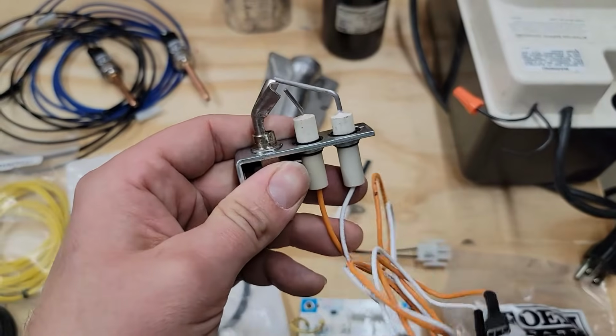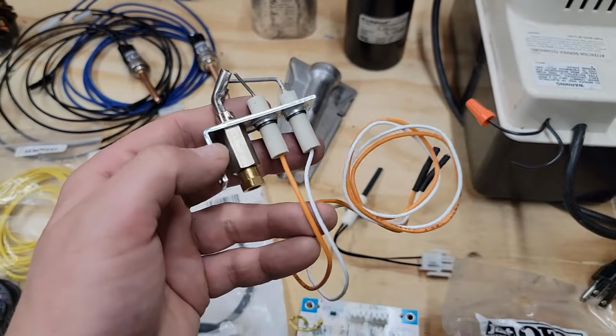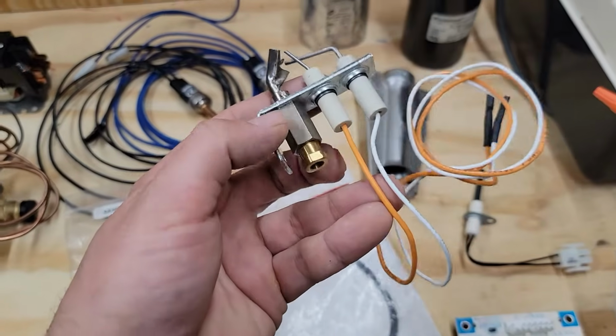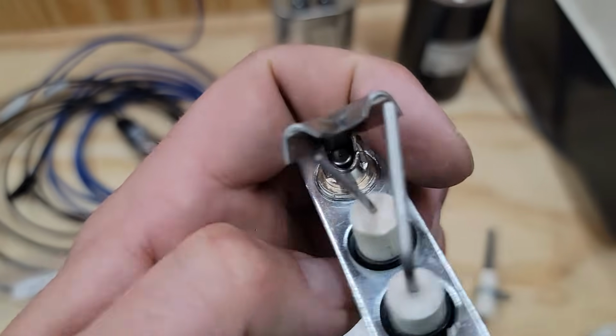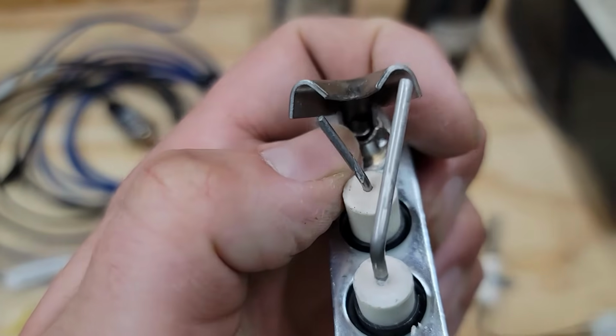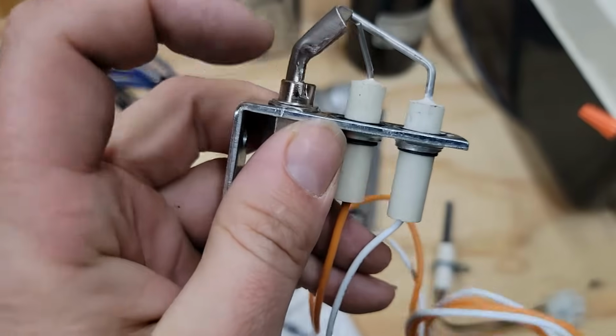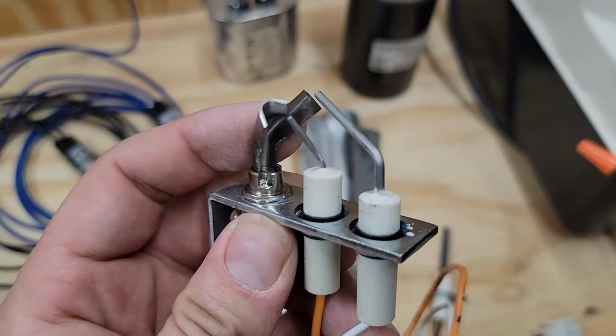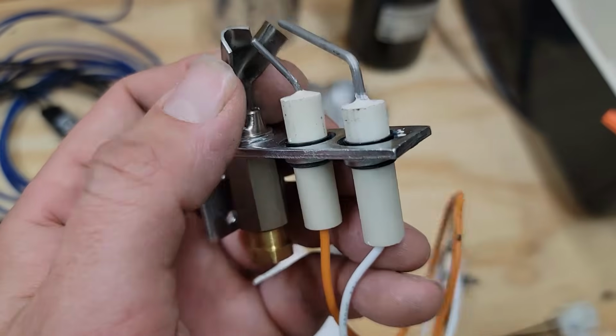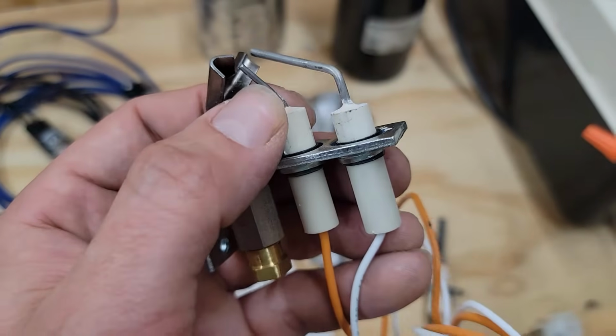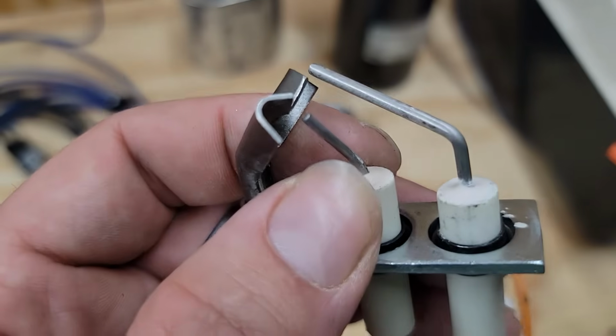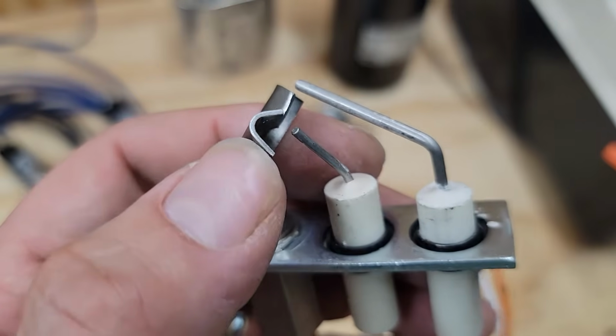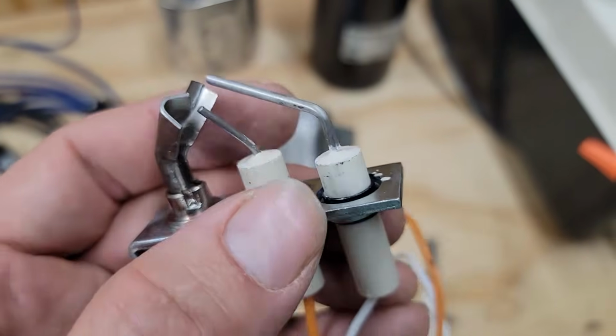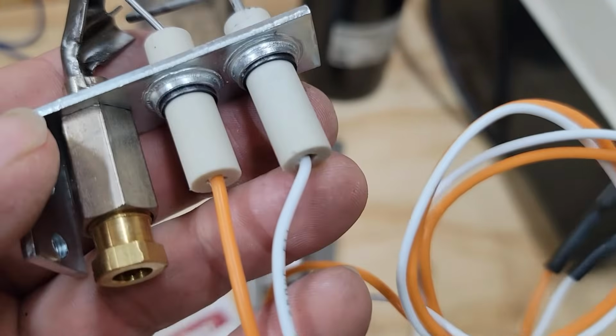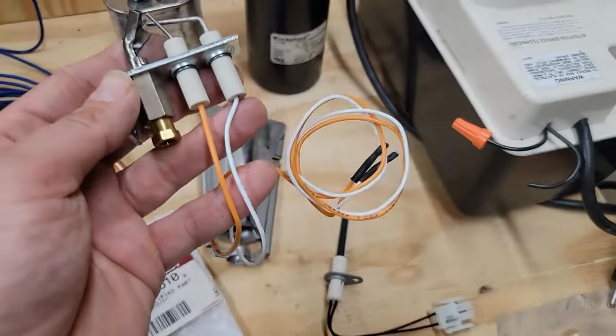So let's talk about, that was a hot surface igniter. This is a spark igniter, and this is a pilot tube assembly. And this is where the pilot tube would come in, and then you've got an orifice right here. See that orifice? You can barely see it, but it's right there. I'm pointing to it right there in this. And this is where the gas would flow in. And then we have a spark igniter. You see that spark igniter? It sparks off of this, okay? And then we've got a flame sensor over here. You see that white wire going to that flame sensor?